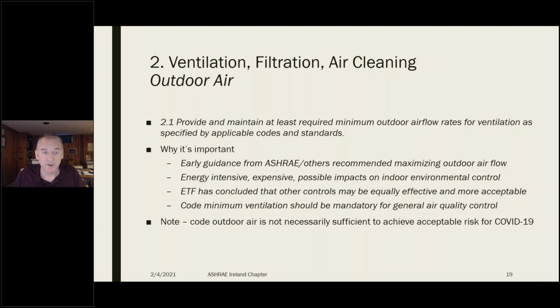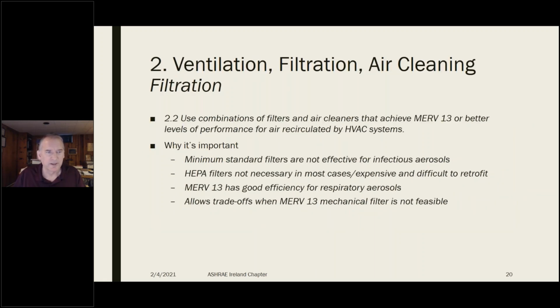But code minimum ventilation should be mandatory because it's required for general air quality. What we're saying, however, is not that it's sufficient. What we have to do is look at the totality of all of the controls that are in place and assess their combined effect, which is another important update to guidance. And moving on to filtration, we've now come out with the statement that we should use combinations of filters and air cleaners to achieve MERV 13 or better levels of performance for treating recirculated air. We still believe MERV 13 is the right efficiency level to target for filters, or ePM1 50 if you're in Europe.